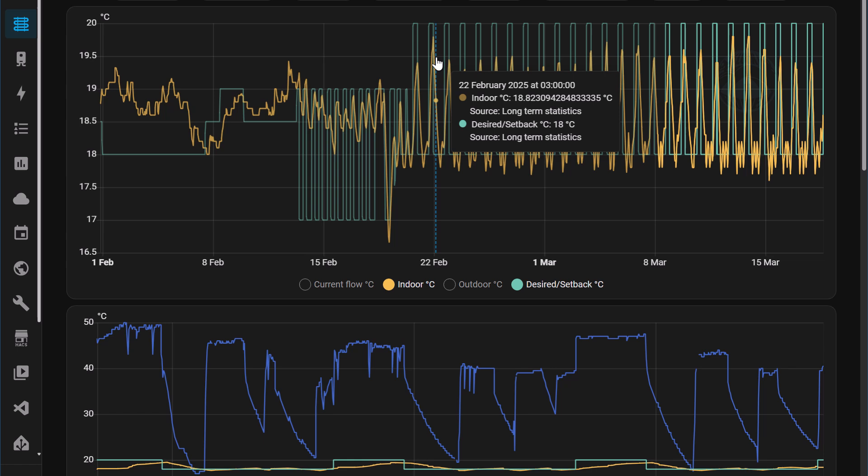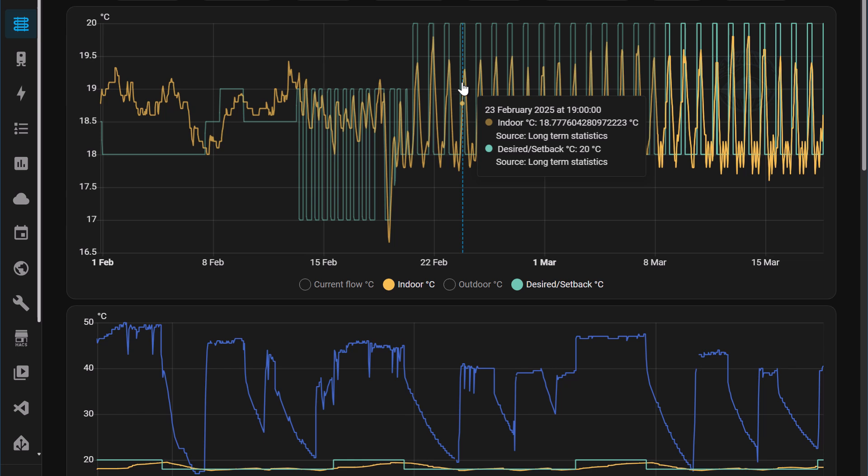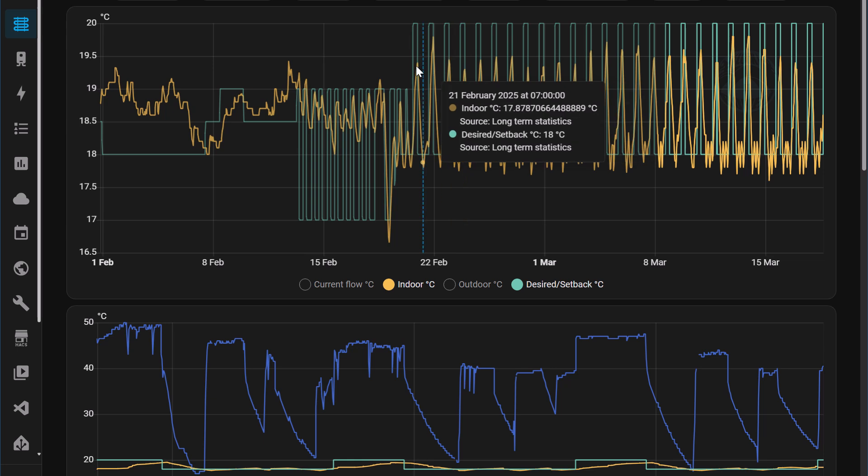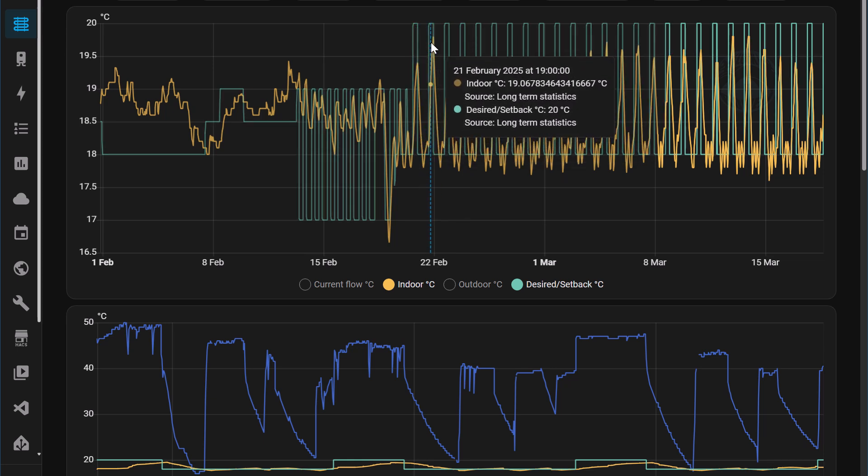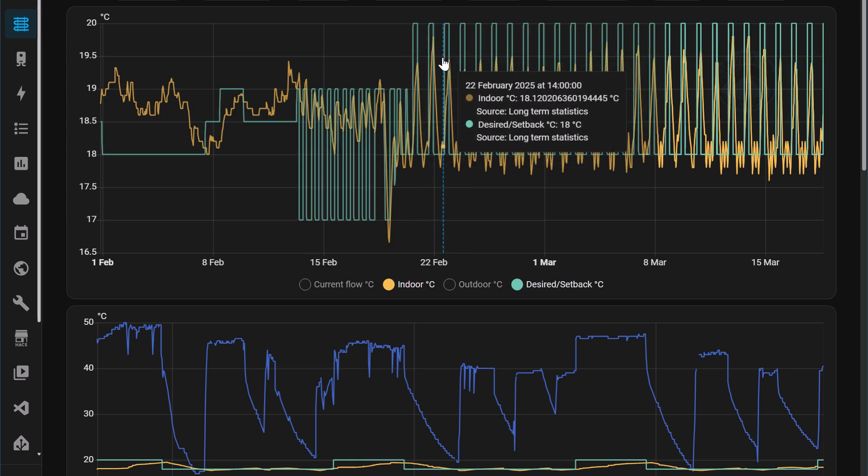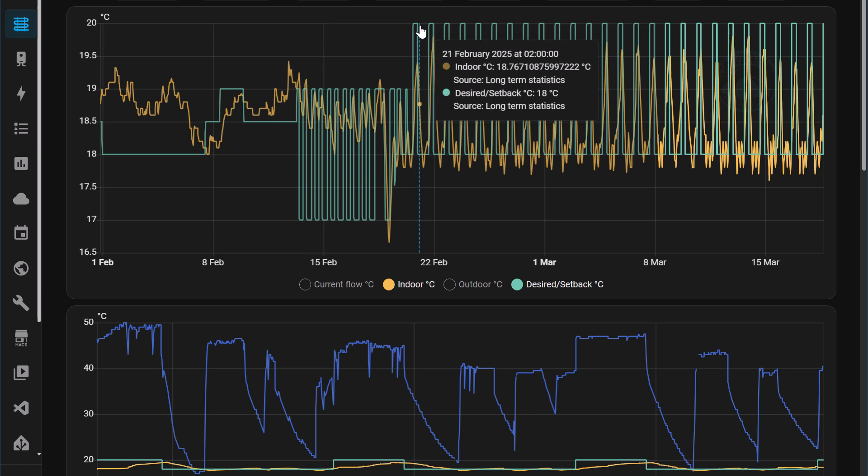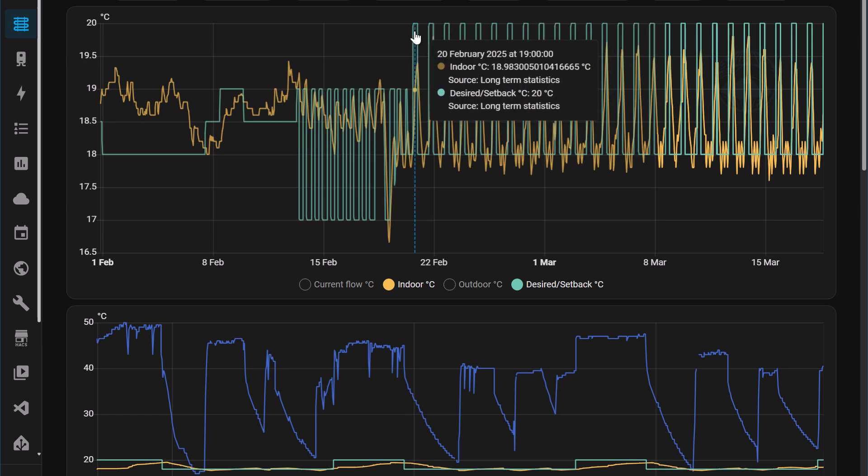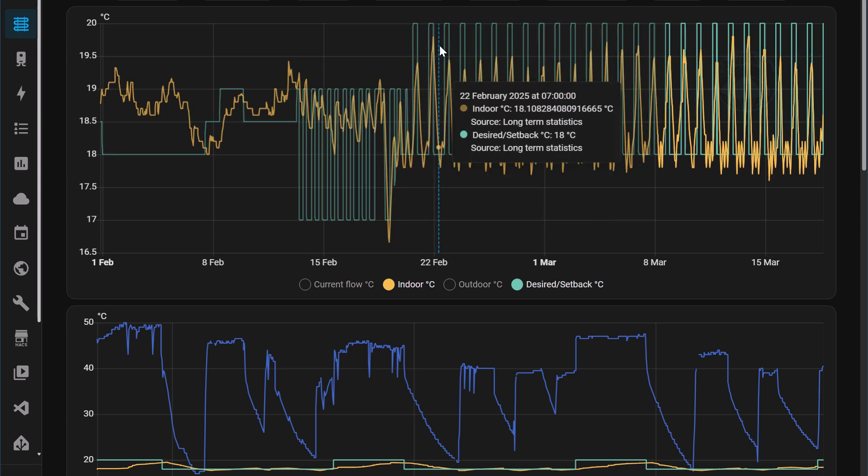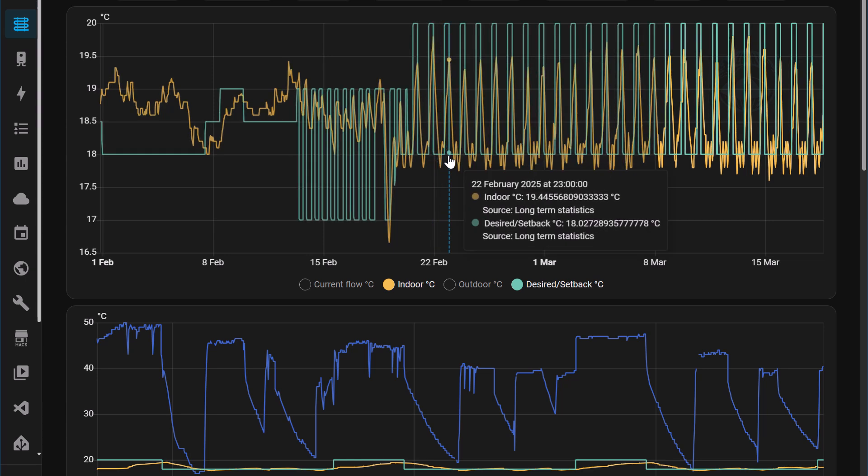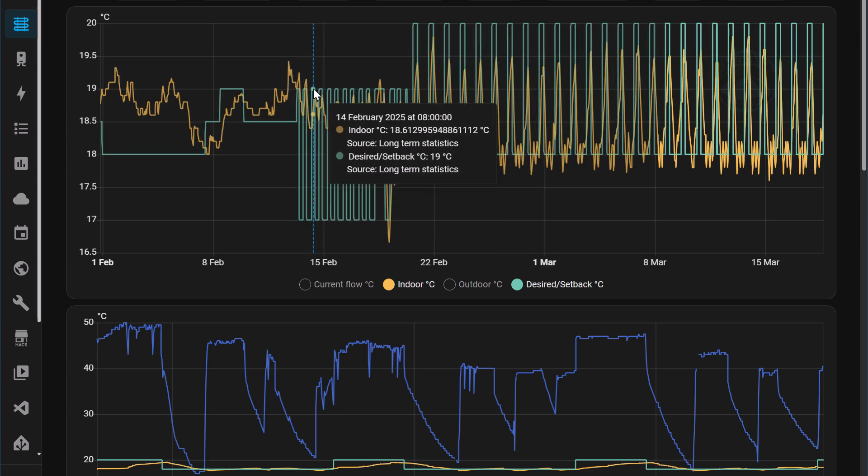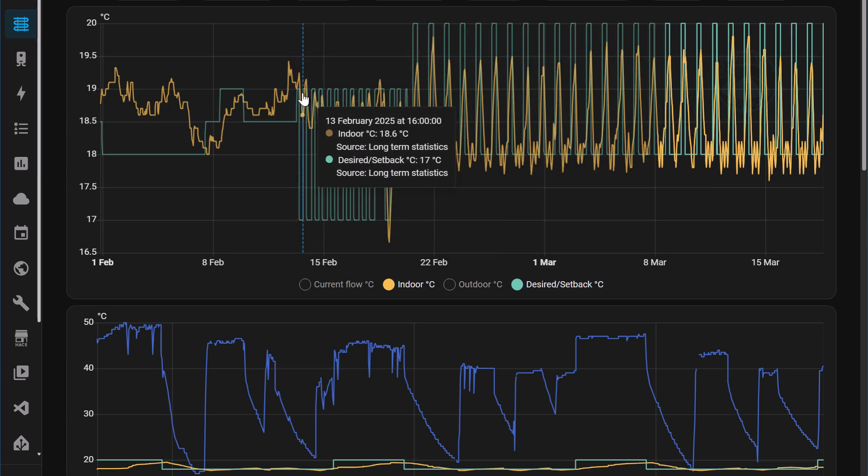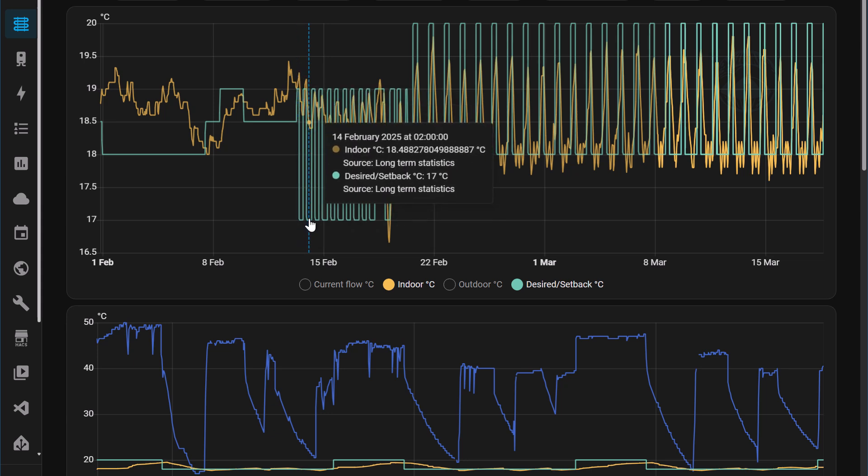Now I never wanted the temperature, the indoor temperature to be 20. And given I'd already tested the heat curve at 1.3 in late January, I knew that I would never really reach the desired temperature of 20. And that was actually a good thing. What I did was set the desired temperature to 20 and the setback temperature to 18. So it's still a two degree window from top to bottom like it was when it was on active. I had it here at 19 and 17.